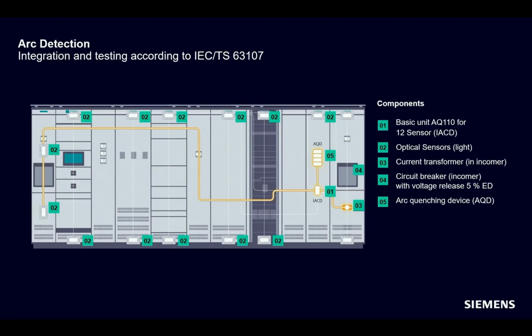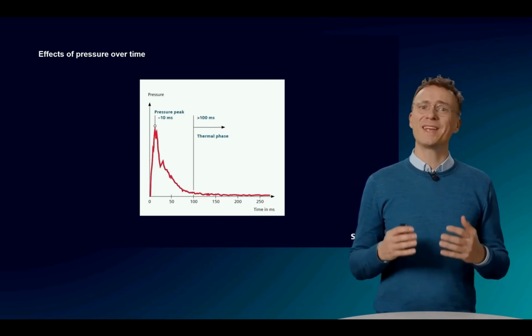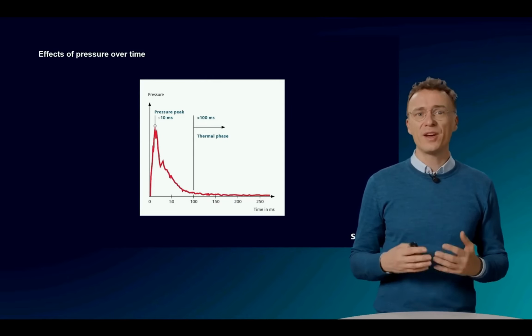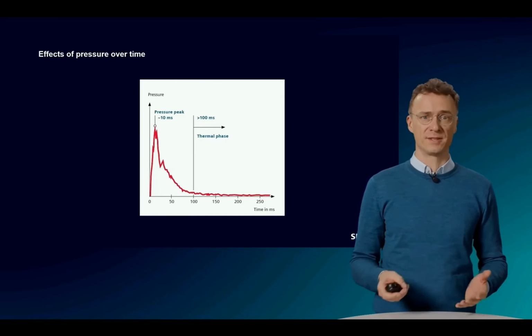In order to ensure protection, even in the event of an arc fault occurring on the primary side, in which case the CTs would not measure a current flow, there is also a special pressure sensor that trips the upstream distribution in medium or low voltage. To be able to reduce the stress even further, I would like to remind you once again of the pressure curve. This system can also be combined with a quenching device. This reacts so quickly that you can get ahead of the peak of the pressure curve and can thus also reduce the mechanical load on the system.